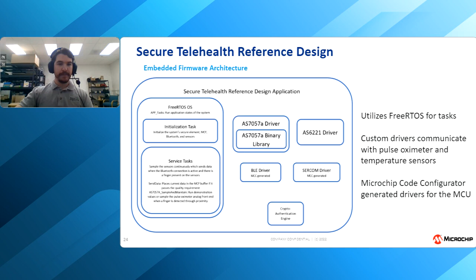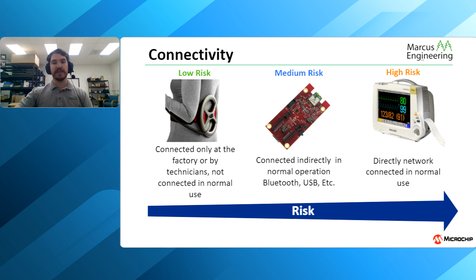So moving forward to talk about some of the FDA documentation that Martin alluded to earlier, if a medical device contains any sort of software or firmware, it will most likely require cybersecurity documentation. This can affect the development process based on 3 main components, which are connectivity, software complexity, and device risk. So jumping right into connectivity, as you can see here, as the device gets more connected to networks or external sources, the risk increases, which also means the requirement for cybersecurity testing and mitigations for different risks increases as well. This means more work must be done during the process to ensure safety and security as your device is more connected to the network and systems around it.